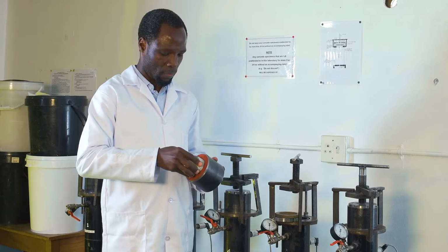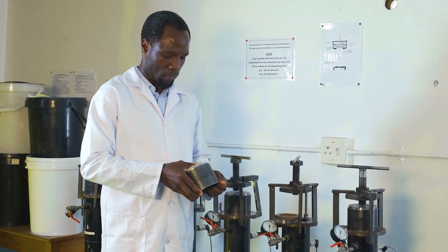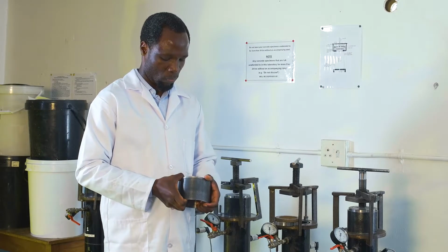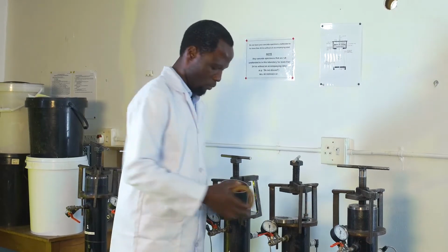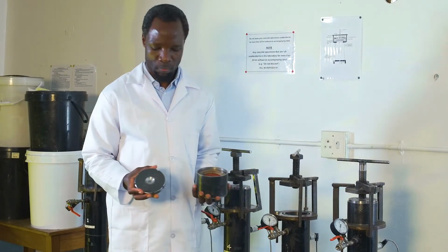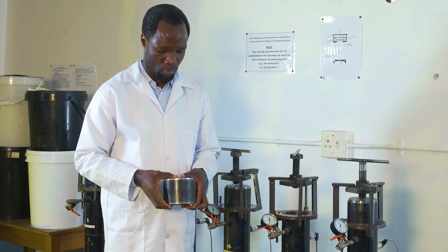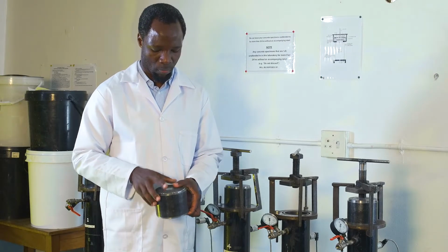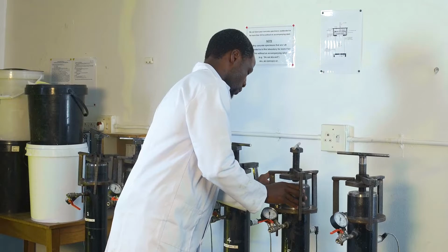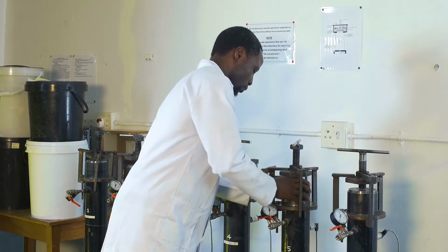The oxygen gas is supplied from a pressurized cylinder. It is important to ensure that the disc is placed correctly in the compressible collar. This is done for 2 reasons. The first reason is to ensure that the outside disc surface will be in direct contact with the oxygen in the gas chamber. The second reason is to ensure that the correct volume of oxygen is contained in the gas chamber at the beginning of the test.